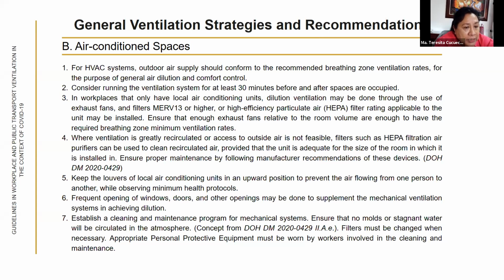Okay, if ventilation is greatly recirculated or access to outside air is not feasible, we really try to limit recirculated air, especially because we know that if there is any contamination and there is no filter that is going to purify it, we have to ensure that, because of the recirculation, there should be a HEPA filter present in the air handling unit, because that is the only way we can remove the contaminants from the recirculated air.